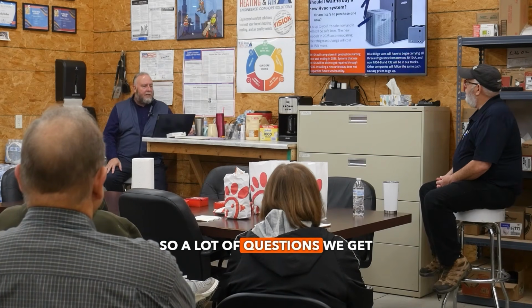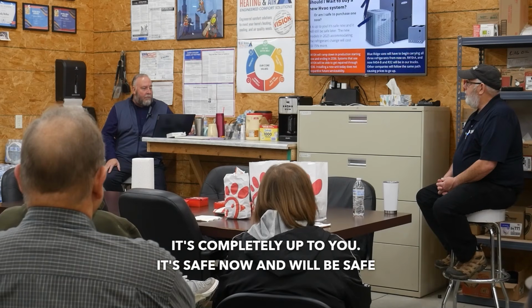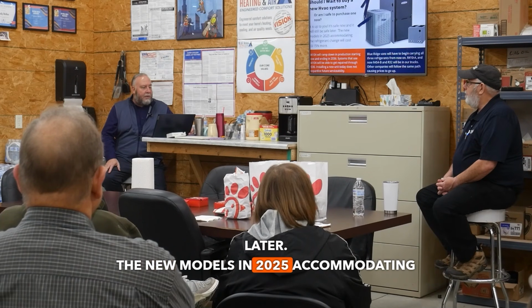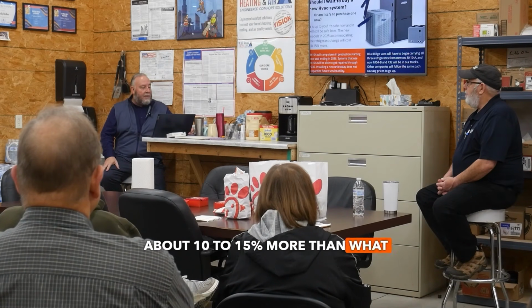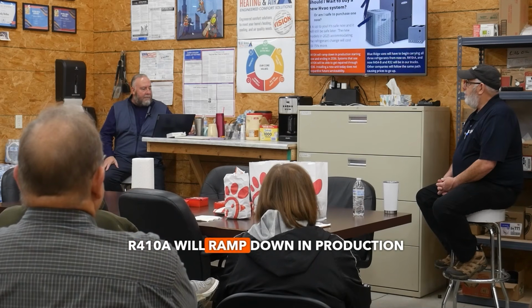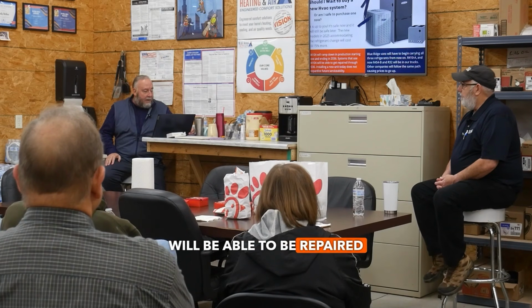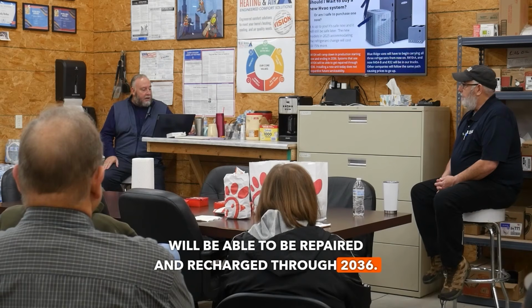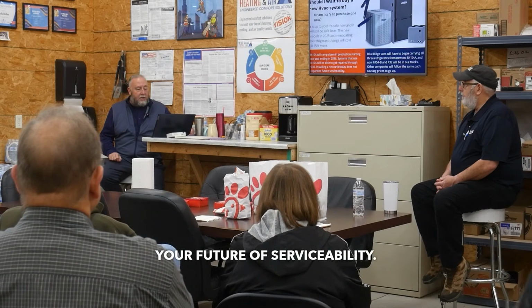So a lot of questions we get is, should I wait to buy a new system or am I safe to purchase one now? Well, it's completely up to you. It's safe now and will be safe later. The new models in 2025 accommodating the new refrigerant will cost about 10 to 15% more than they do now. R410A will ramp down in production starting now and ending in 2036. So systems that use R410A will be able to be repaired and recharged through 2036. Installing a new unit today does not jeopardize your future serviceability.